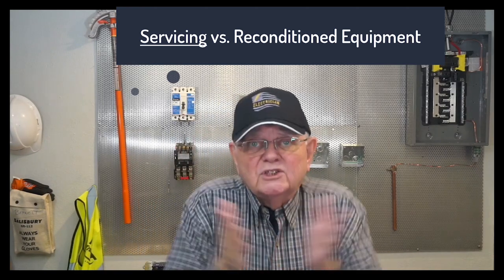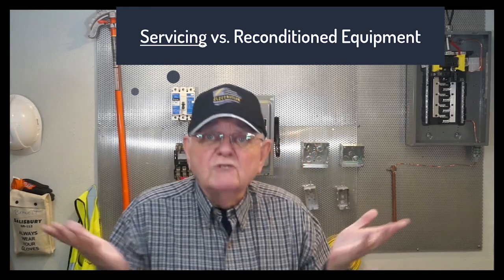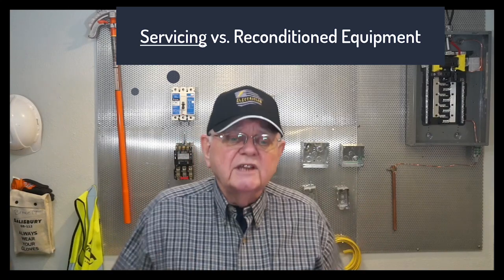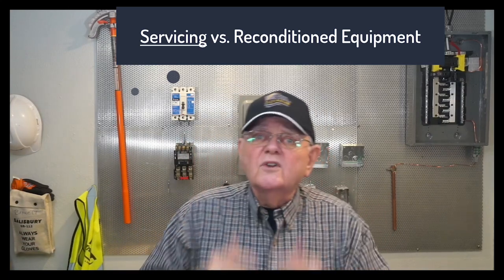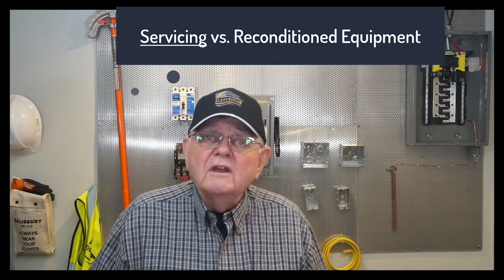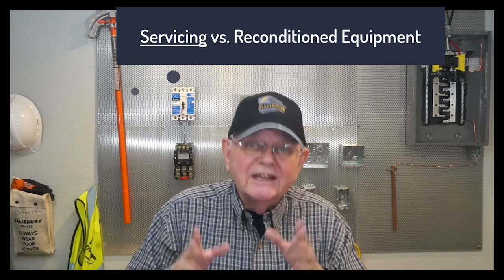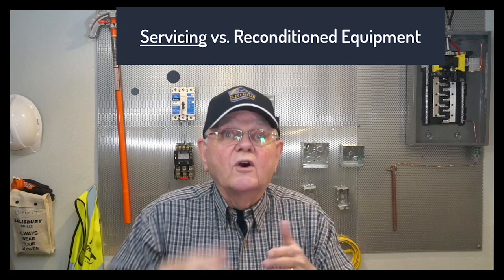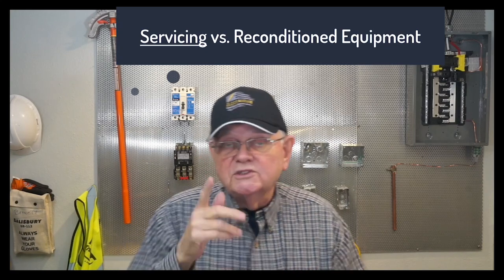Now, if I'm going to service equipment, I service my equipment, right? NFPA 70B now, the standard for electrical equipment maintenance, I follow that. If I'm going to recondition it, remember there are requirements for labeling on that equipment. So you'll want to take a look at that. So those are some of the new definitions that we have in Article 100.